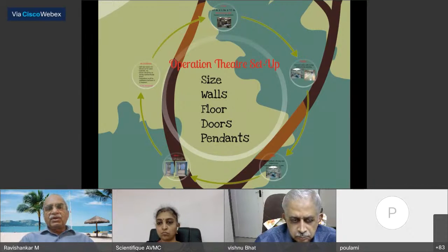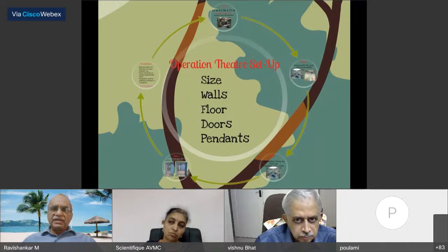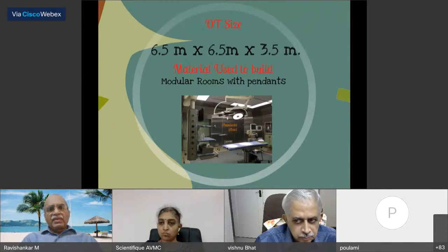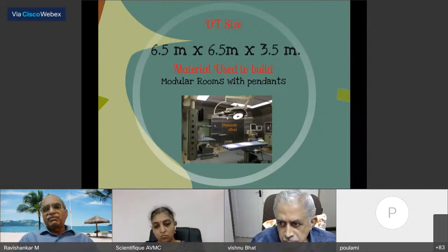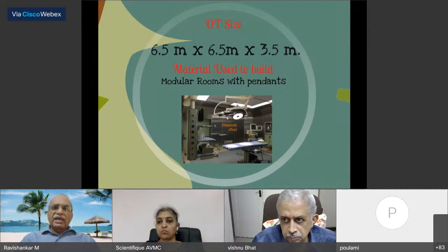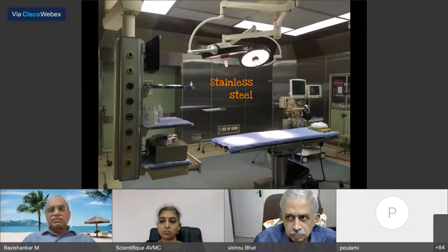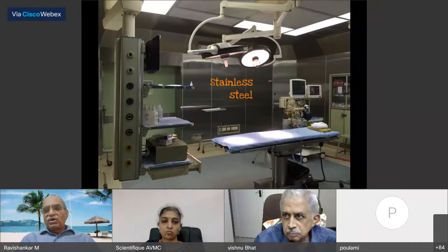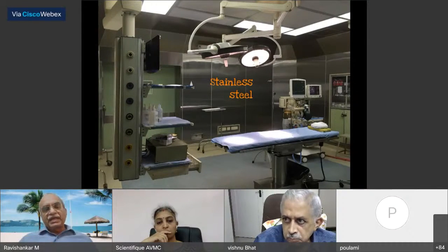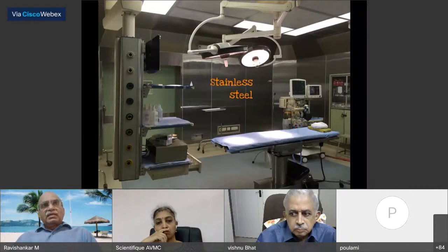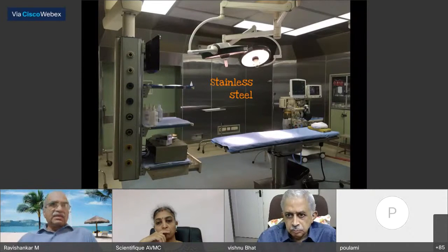Coming to the operation theater setup, let's look at the size, walls, floor, doors, and pendants, and how it should be. The specification is that the minimum size of a theater is 6.5 meters into 6.5 meters with a height of about 3.5 meters. The material used in the modular rooms with pendants is predominantly stainless steel. The advantage of stainless steel is it is easy to clean and maintain, and the initial cost might be high, but the recurring cost will be less.